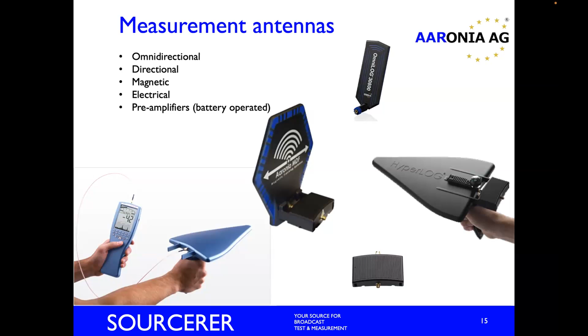More RF. In many cases you need to sweep filters, look at a cable, look at your antenna, maybe an amplifier, all kinds of things that you might need a network analyzer for. And again, this is a form factor that is much smaller than a classic network analyzer. You know, everybody kind of has maybe still an HP 8753 in the house, or a Rohde & Schwarz, or an Anritsu, or a Wiltron even from the old days, and they're all big and bulky. And if you want to take them out in the field and do your measurement, it's very, very cumbersome, and you need AC power. So Copper Mountain Technologies is a company out of Indianapolis, and they make compact network analyzers.